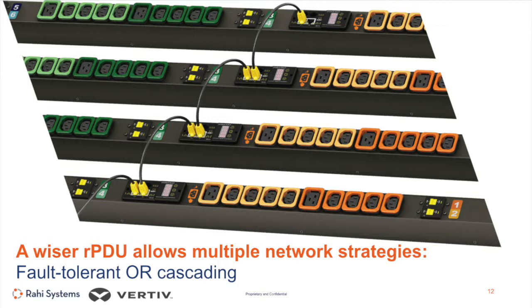So it often comes down to how a particular consumer of rPDUs interacts with his or her IT department. Is that IT department more concerned about minimizing network ports that a PDU would occupy, or is it more cumbersome to have to give a unique IP address to each one of these PDUs? That's something that would have to be done, the unique IP address, if I were to choose this fault-tolerant approach. So a wise PDU would give its users the option of how they want to manage the network resources.